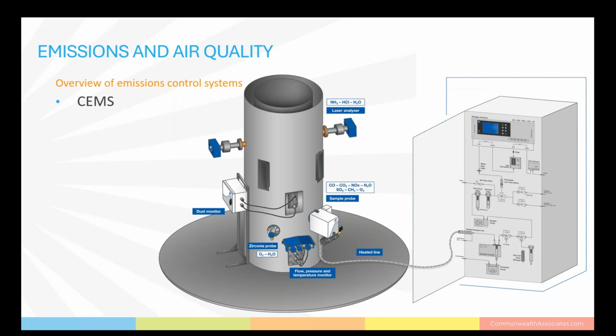One key method of control is by using a continuous emissions monitoring system. A CEMS unit samples, measures, collects data, records, and reports the gas emissions information. They can also measure and report gas flow, gas opacity, and moisture content, and will include all of the components necessary for required emission measurements.